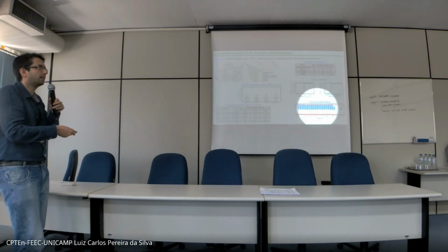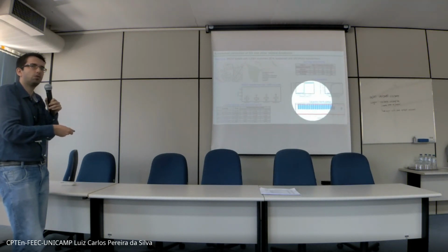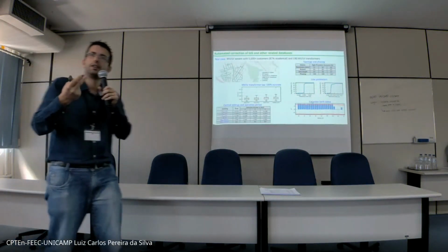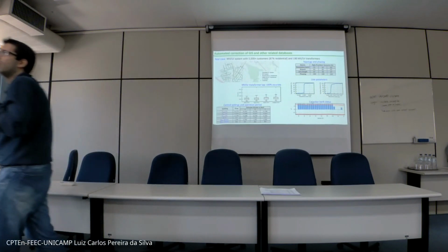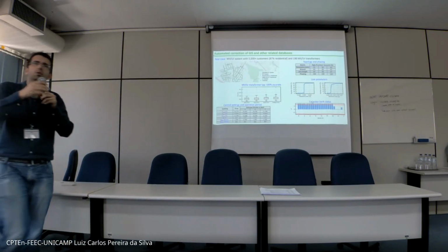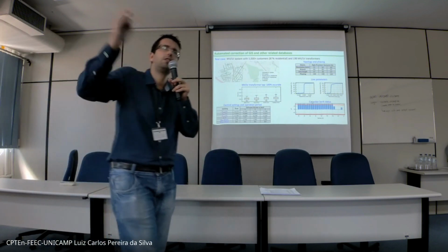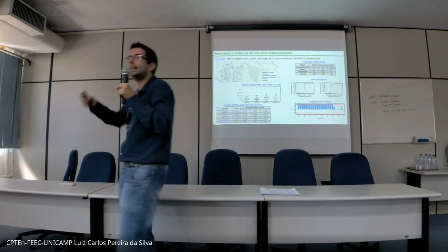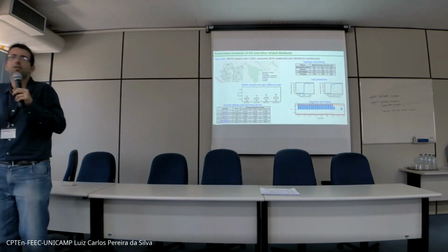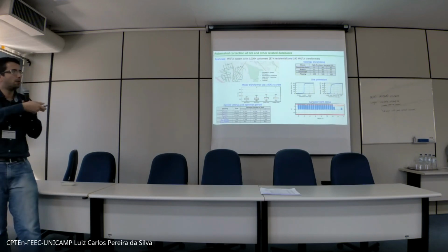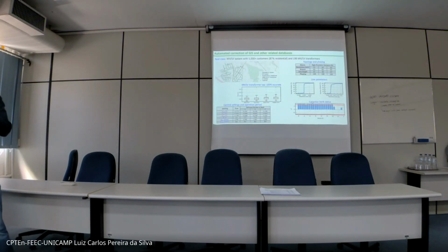You can detect capacitor bank status, whether it's connected or not. There are situations where one phase of the capacitor bank remains disconnected for weeks or months, and the utility doesn't even know, because it's not monitored. With smart meters, we can detect this status.